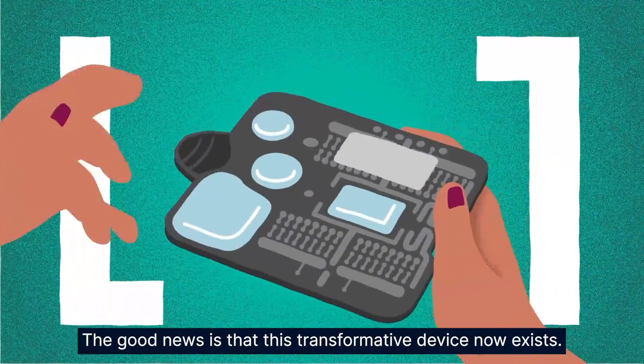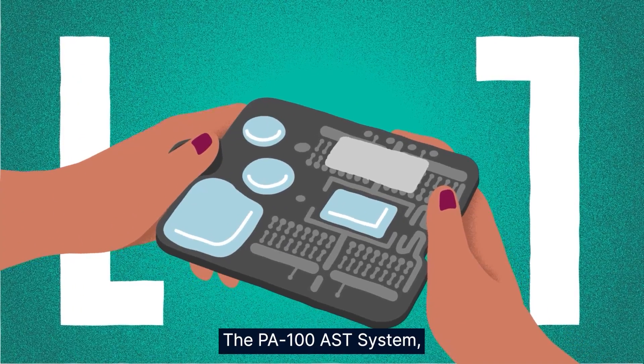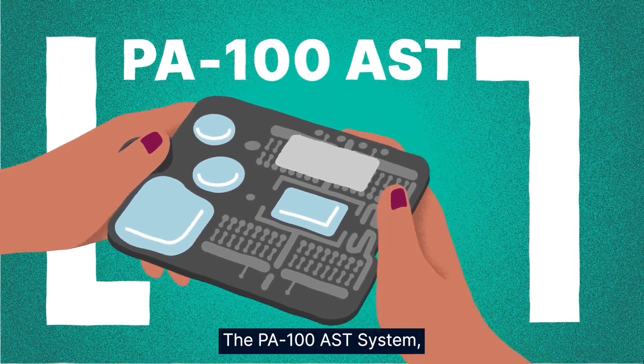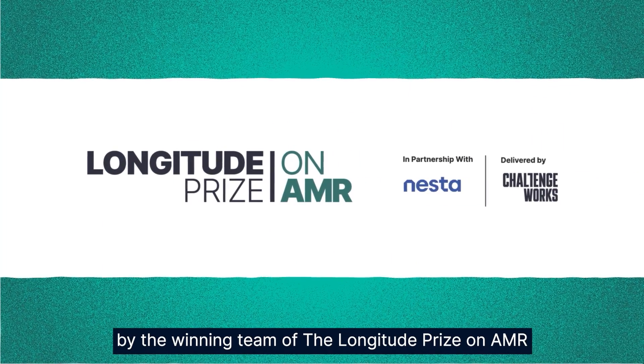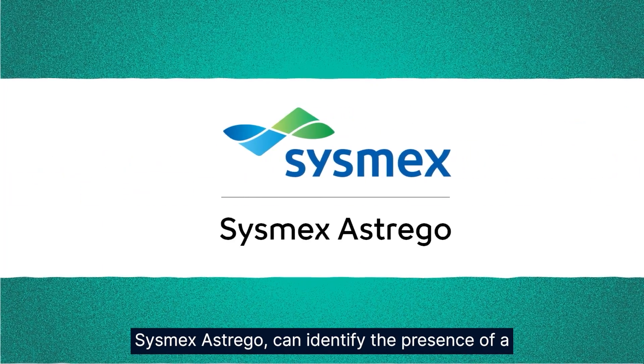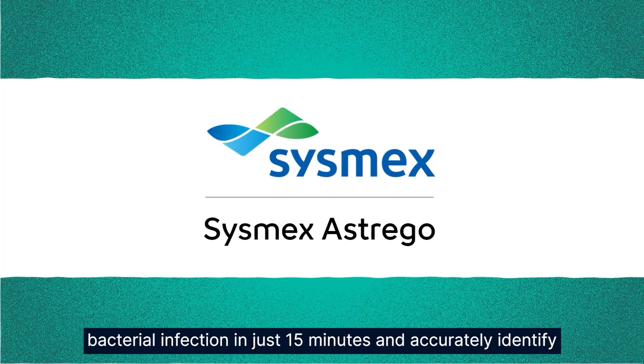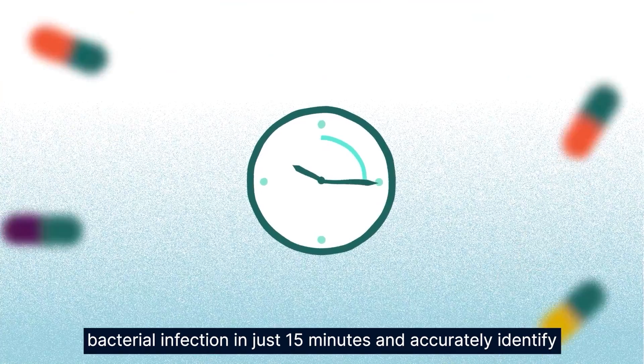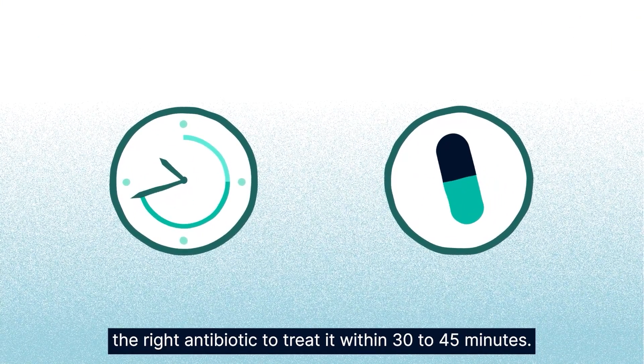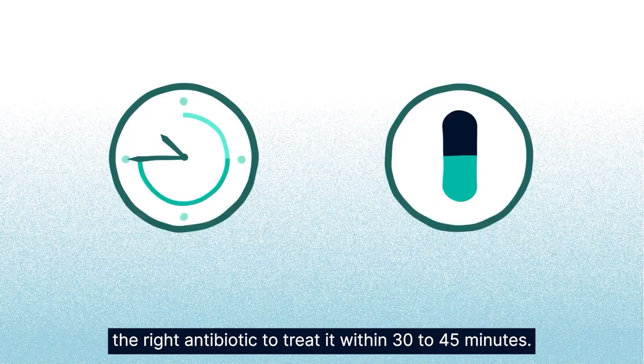The good news is that this transformative device now exists. The PA100AST system, by the winning team of the Longitude Prize on AMR, Sysmex Astrego, can identify the presence of a bacterial infection in just 15 minutes and accurately identify the right antibiotic to treat it within 30 to 45 minutes.